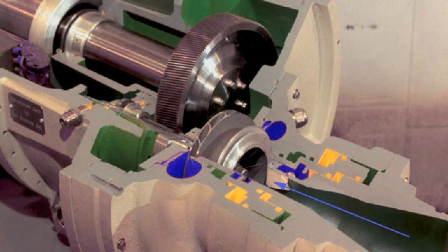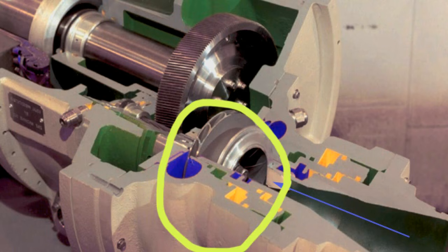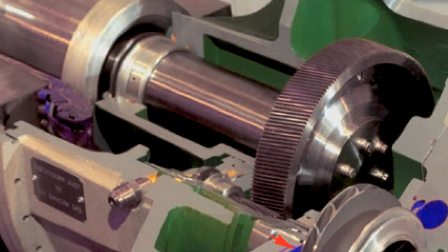So you can clearly see here the inlet from the suction line going into the impeller section here. We've got the impeller there. We've got the volute, which is in this region here. Then the discharge line just here. The diffuser is this small section just here. And then just at the back here, we've got the impeller shaft, and you can see the gear just there. And then obviously we've got the main gear here, which is connected via this shaft here, which goes directly to the induction motor mounted at the back of the chiller.